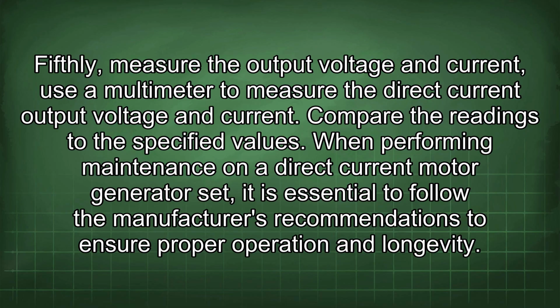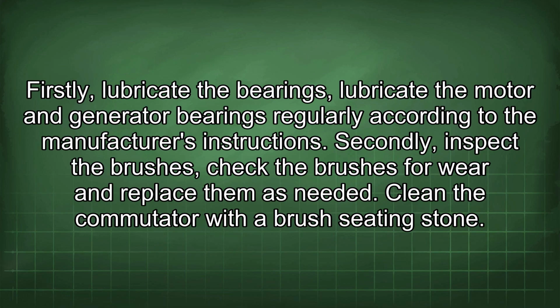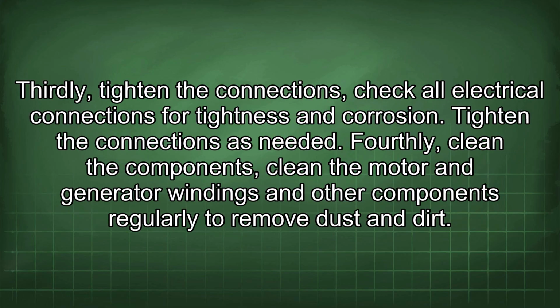When performing maintenance on a direct current motor generator set, it is essential to follow the manufacturer's recommendations to ensure proper operation and longevity. Firstly, lubricate the bearings. Lubricate the motor and generator bearings regularly according to the manufacturer's instructions. Secondly, inspect the brushes. Check the brushes for wear and replace them as needed. Clean the commutator with a brush seating stone. Thirdly, tighten the connections. Check all electrical connections for tightness and corrosion. Tighten the connections as needed.